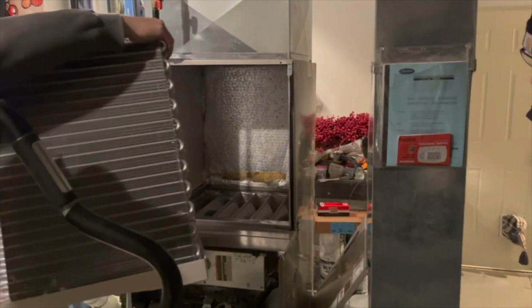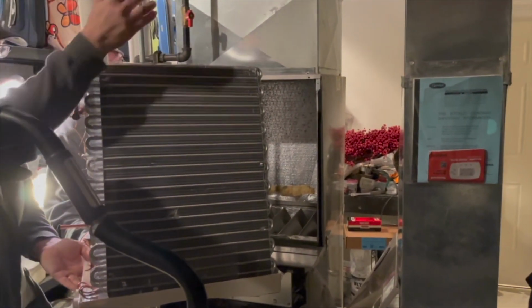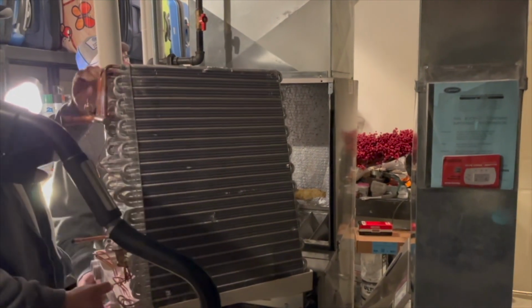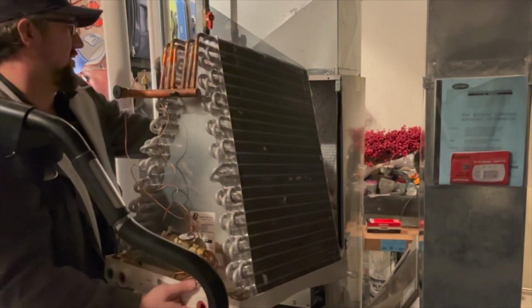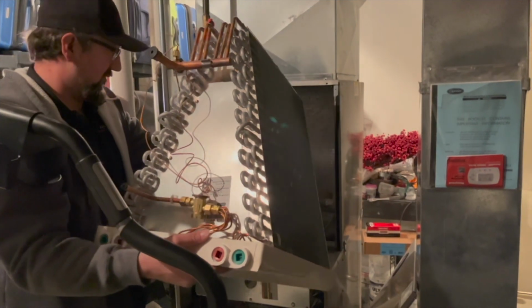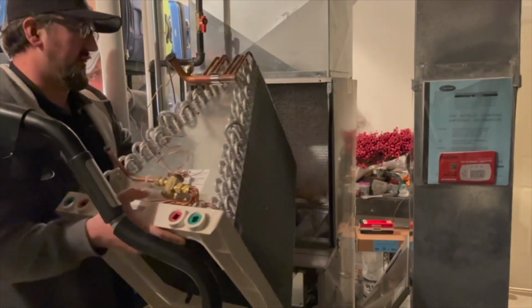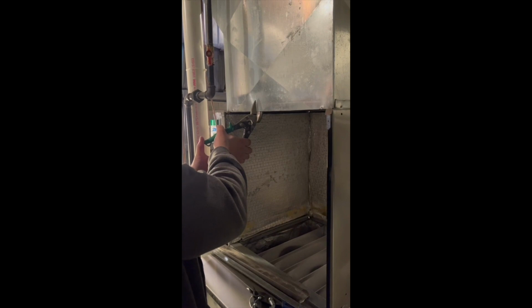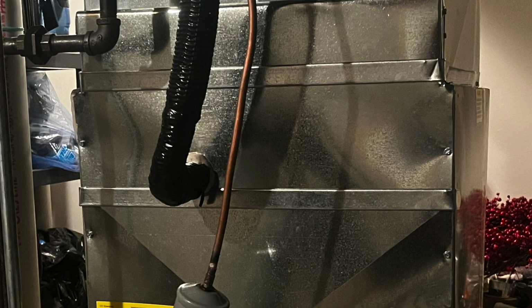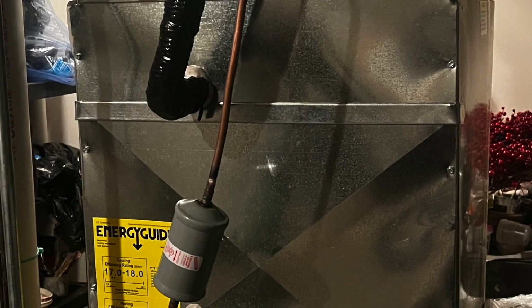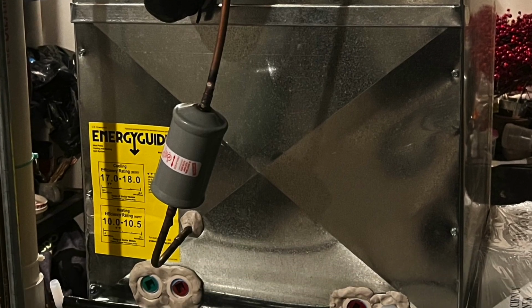So it's a little bit of nitpicky work, but we want that coil to attach very securely, level. You get it. So now that we've got the pan, but the coil is a little bit taller than the coil casing. We were hoping to tip it in, but it's not going to fit. So a little bit more sheet metal work, and with some sealing, and voila, the coil's in and the unit's sealed back up.